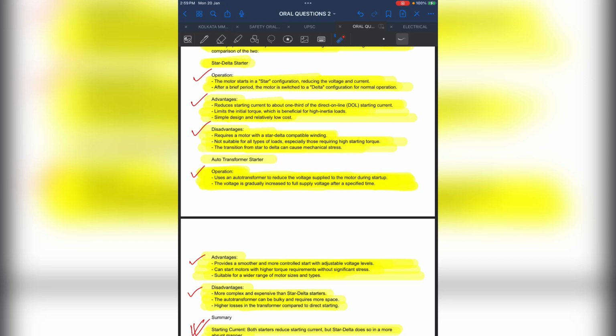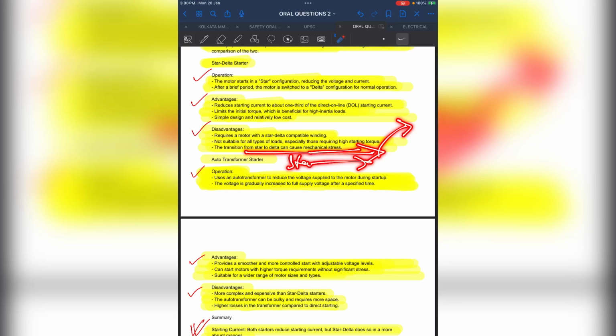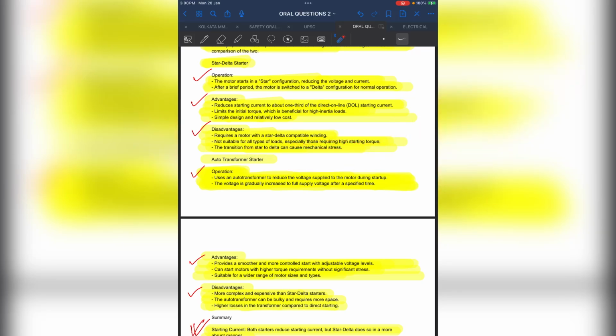You have to go for the auto transformer starter. The transition from the star to delta can also cause mechanical stress. There is a change from star to delta, and due to this a sudden voltage surge will occur, and due to this mechanical stress will happen.